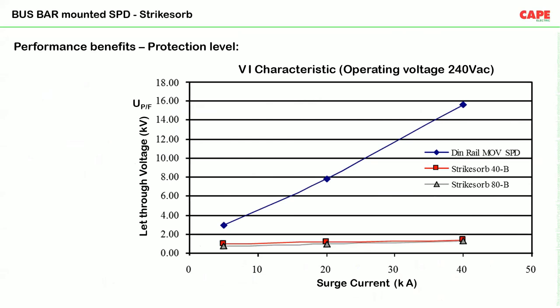See, now there is a graph where we have compared two types of SPD, DIN rail mounted SPDs and bus bar mounted SPDs. Now, in India, generally what we are using as of now is a DIN rail mounted SPD. You can see with increase in surge current, the UPF is increasing in a DIN rail mounted SPD. For example, with 40 kiloampere surge current, UPF is around 16 kV. Whereas in case of bus bar mounted SPDs, there is a very, very slight increase in UPF. Even for this 40 kiloamps of surge current, UPF is less than 2 kV only. So in terms of reliability and voltage protection level, the bus bar mounted SPDs provide very good performance.